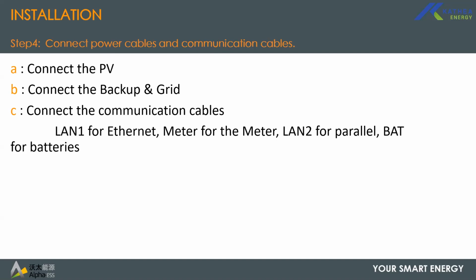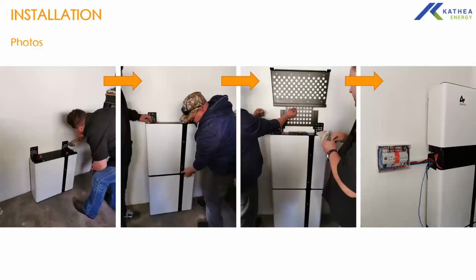And then you need to connect your communication cables, LAN, Ethernet to LAN, meter to meter, LAN 2, which is the inverter to inverter port for paralleling, and then the battery comms cable for the battery BMS connection. So this is basically one of our clients who was doing the installation. So I see the first battery, second on top of the first, and then that is the inverter bracket, and then you just hook the inverter on the bracket, and then it will rest on the battery.